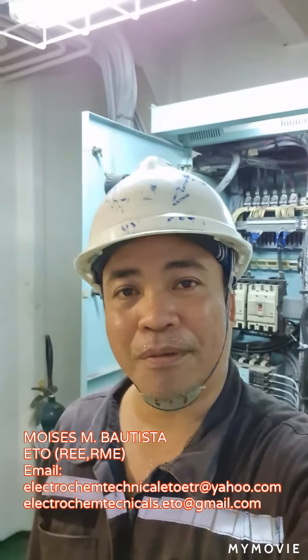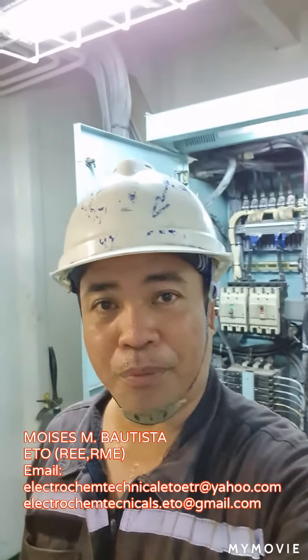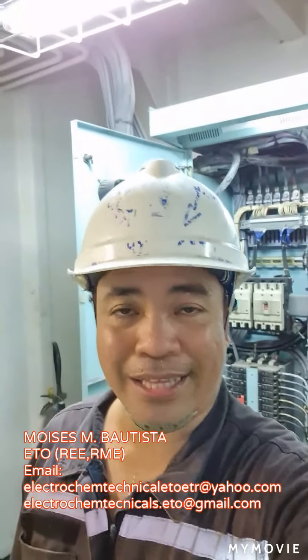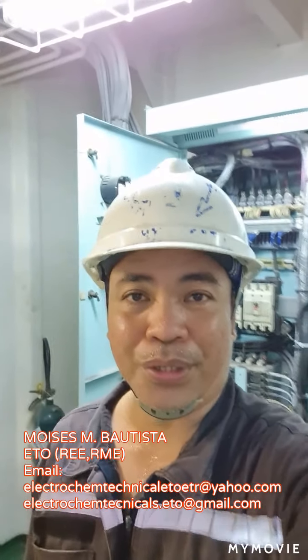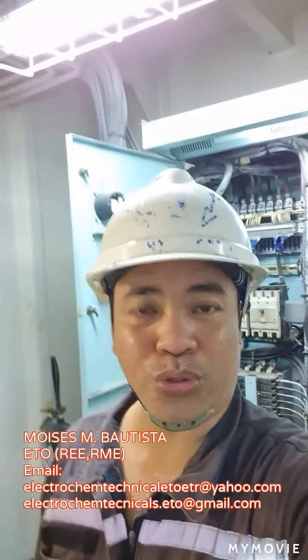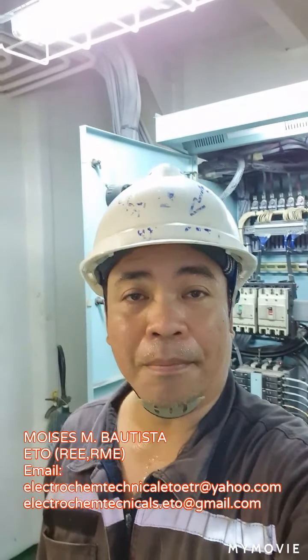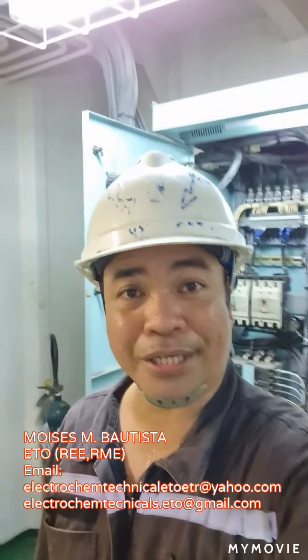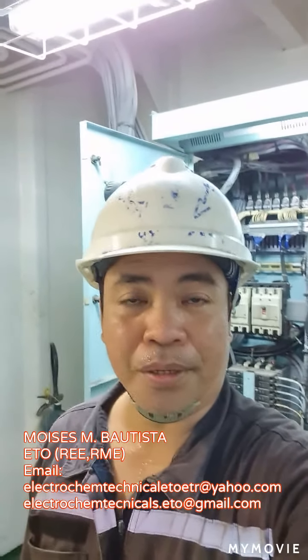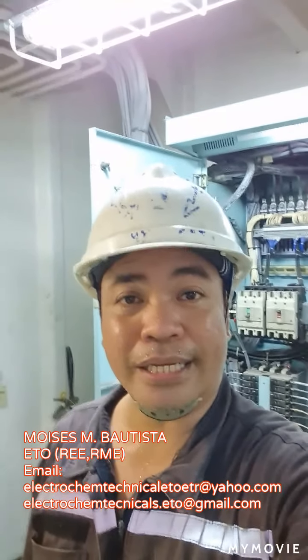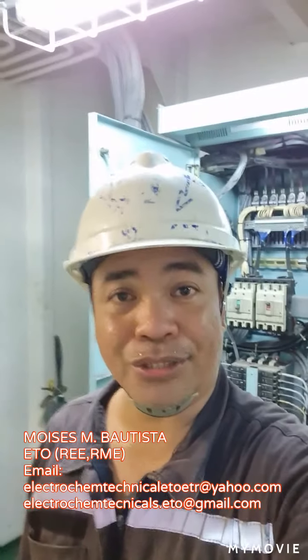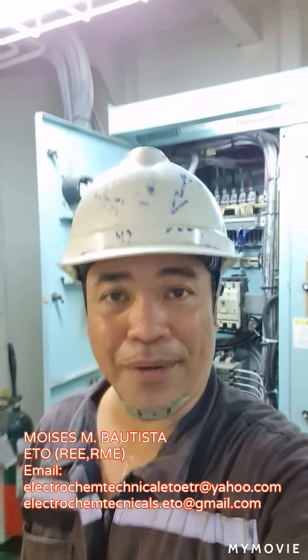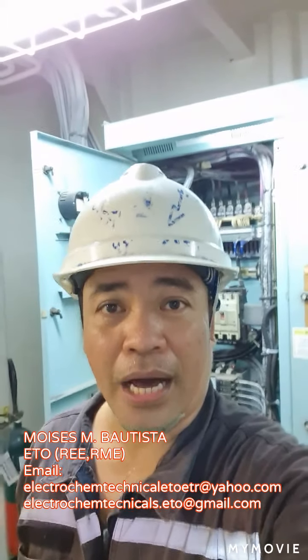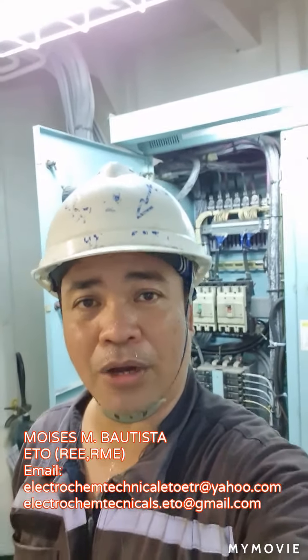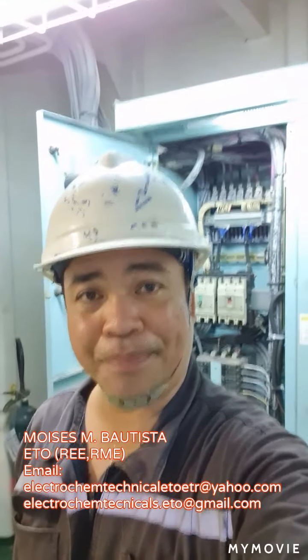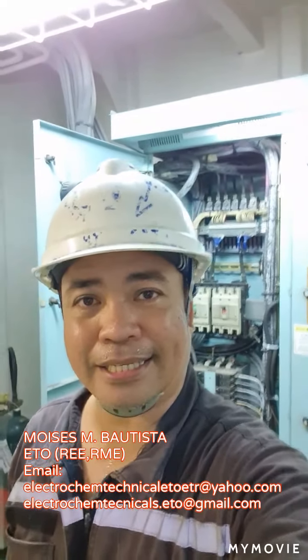But remember, before the shore power voltage is fed to the main switchboard, you must switch on the main switchboard air circuit breaker in the control room, provided that all generator circuit breakers are off. Please take a moment and I will show you how all of these things are accomplished during a ship's dry dock.